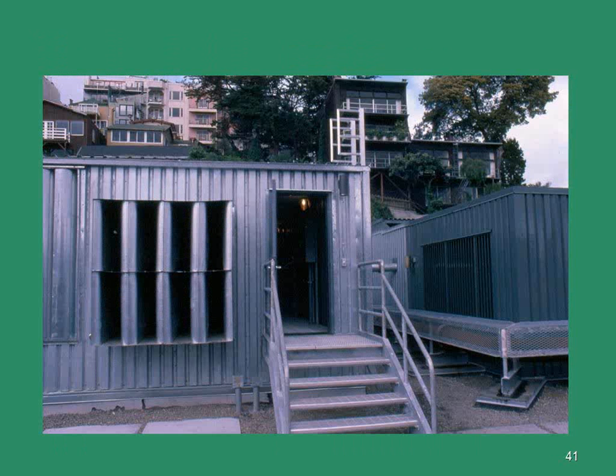So what you're looking at here is the internal side of the silencers that you saw from the external view, and these are acoustical louvers. This is actually a sound absorptive surface. Now, the one-time sound absorption helps you in terms of noise control when you put it inside the box or inside the duct - it helps a little bit there, and it's like having a light bulb in a room. You put in a 100-watt light bulb, you get a certain number of lumens, but you have a perceptibly brighter room if it's painted white versus painted black. So the absorption is essentially painting the room black.